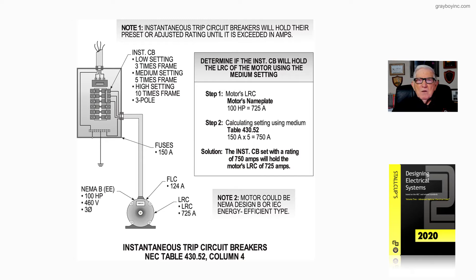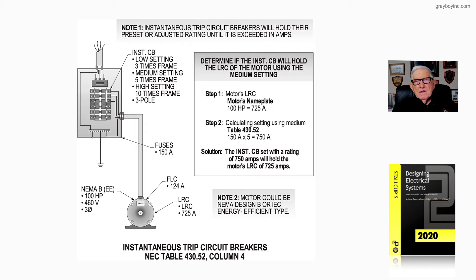Basically what we would do is check out the starting current of the motor. If you had a design letter you could use that to do so. For example, if you're using a design B motor and go to table 430.251(B), you can get the starting current of that motor if it's not a high-efficiency motor. But notice in the callout in the illustration — it's a high-efficiency motor, 100 horsepower, 460 volt, three-phase, so the starting current could be high.